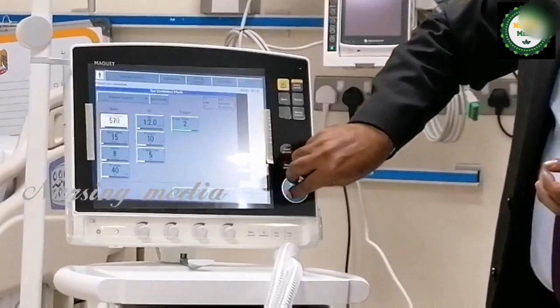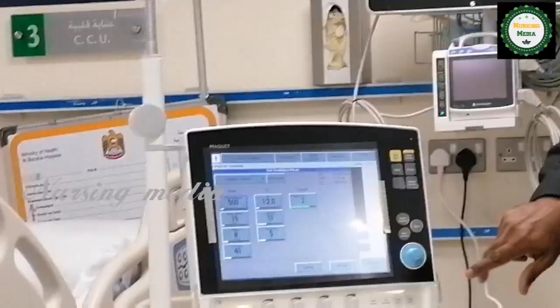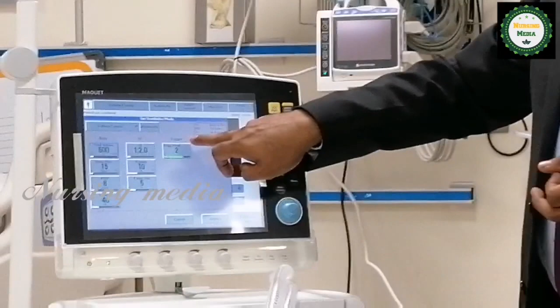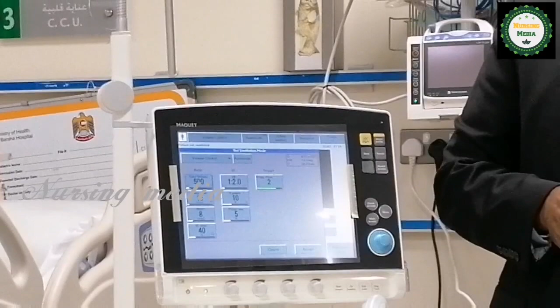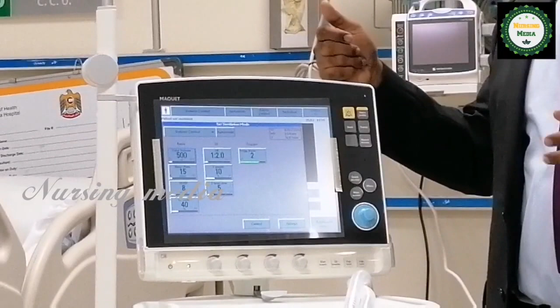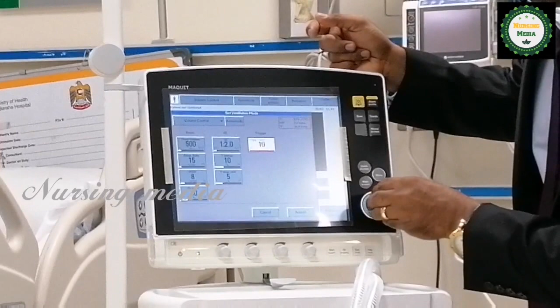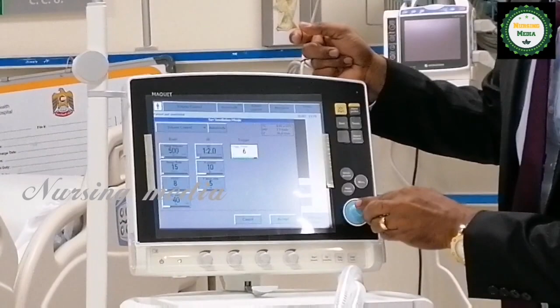Again, tidal volume, rate, PEEP, whatever. You tap here and increase and decrease it with this one and confirm that. Same way, trigger, the scale of 10 to 1. Here we saw something dynamic. This is the latest release, it's 3 years back. It's a little bit older one. Here, scale of flow trigger, 1 to 10. 10 is red. You don't keep 10. 9 is red. 8 is red. You will start with 6. All the other things are same.